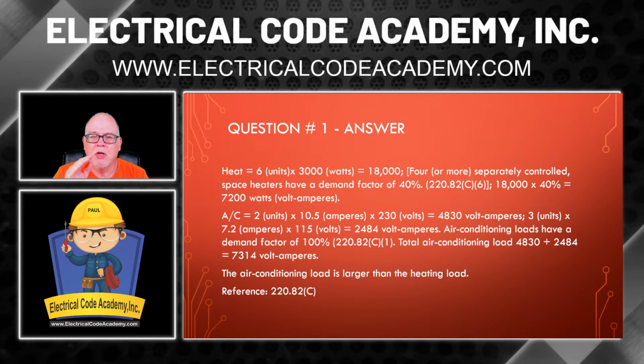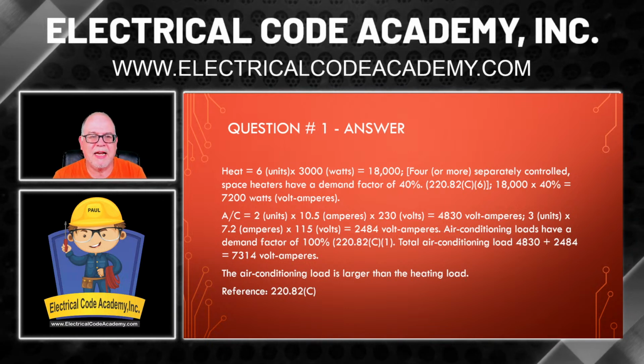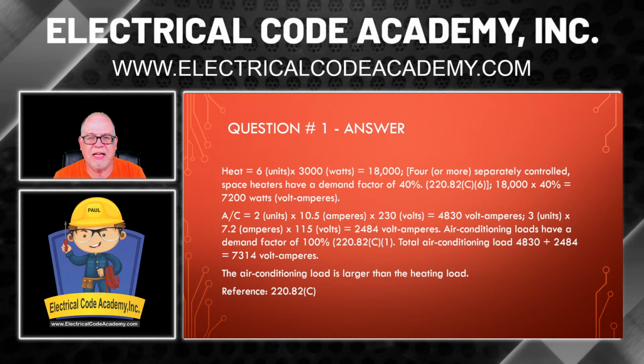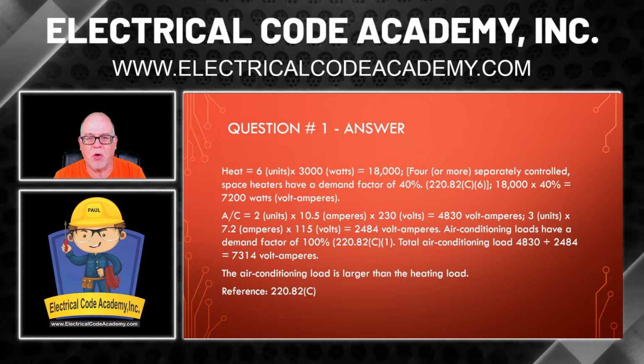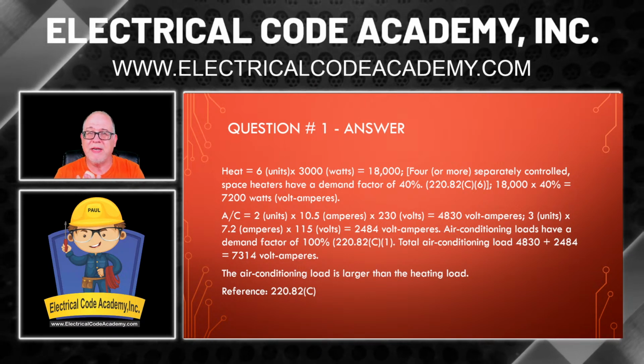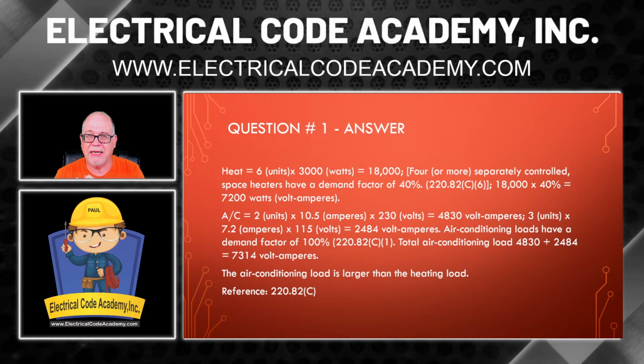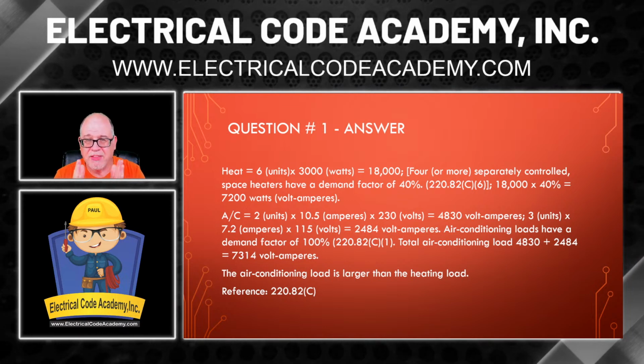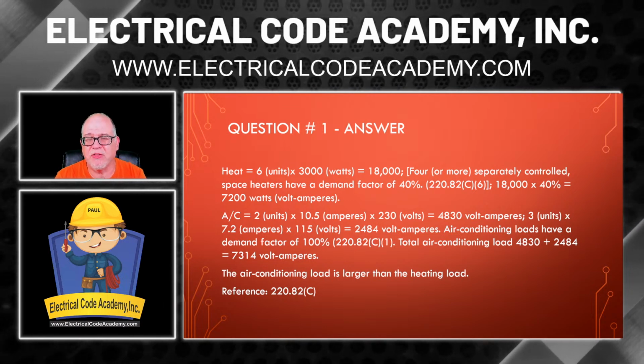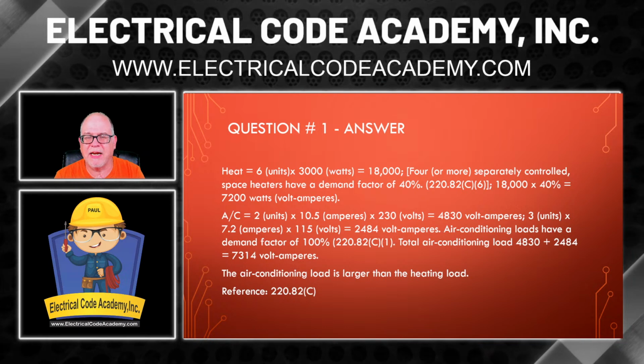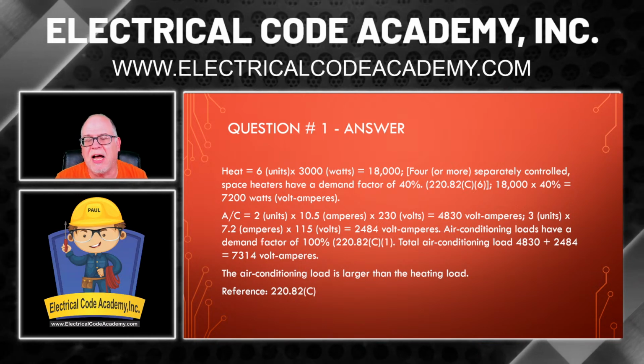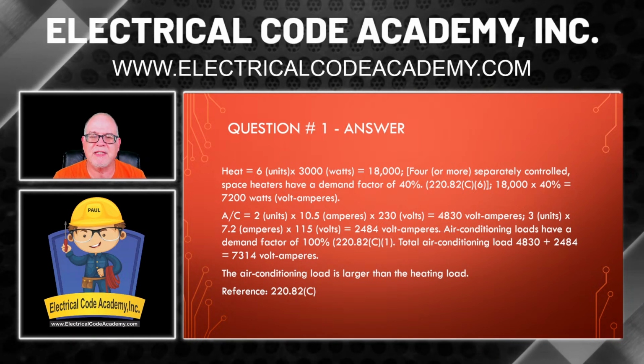All right, so now we want to do 3 times 7.2 times 115. That's 2,484 VA. So all we're going to do is, remember, we take them at 100%, right? So we're going to add the 2 together: 4,830 plus the 2,484. That's 7,314 VA.